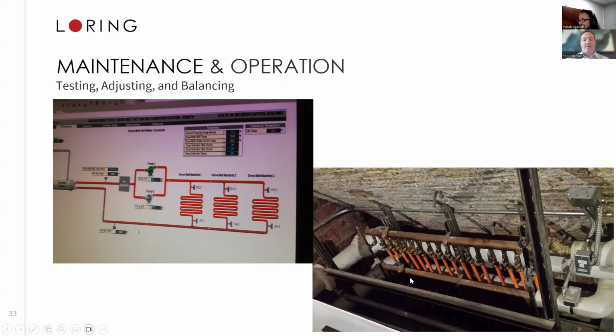They have 3 different zones of controls because they have 3 different zones for the snow melting system. They're measuring the temperature of the water going into each zone, and then the temperature of the water coming out of each zone. But we noticed there was still some ice buildup in what seemed to be patches out on the sidewalks and walkways. We were trying to troubleshoot why this might be, because the flow rate for the system looked good, and the temperatures going in and coming out looked like what we expected.